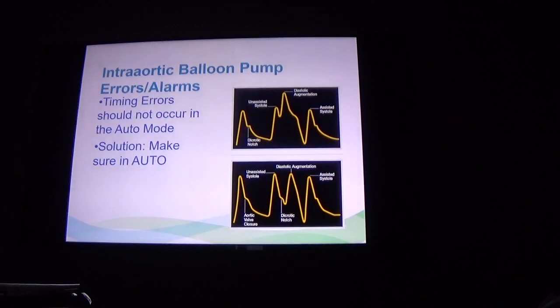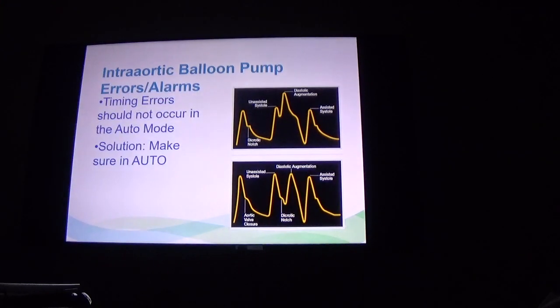Timing errors, the solution to that, pretty much, if you ever have a timing error, put it in auto. Because most of the problems come from people trying to be smart and mess with the device. Nurses, cardiologists, whoever. If people are messing with the device in semi-auto or manual mode for timing, you can get these kinds of errors where instead of being down at the dicrotic notch, the balloon is inflating early, still with the heart in systole. So it's not getting that perfect augmentation. It's not taking that full work off the heart.